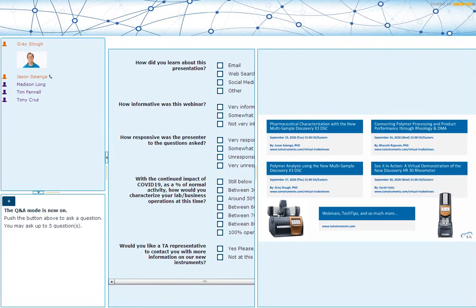The next question deals with the press. Is the sample press compatible with previous pan press sets? Do the new colors correspond to the old colors? I believe so. It depends on how far back you go, I guess. This T0 press is the same T0 press that TA Instruments has been providing for a number of years now. The color schemes are designed to help you match up the appropriate pan type with the appropriate die set that goes along with this press. The press isn't specifically new to the X3, but the press does have the ability to seal T0 pans, which are typically the blue die sets.